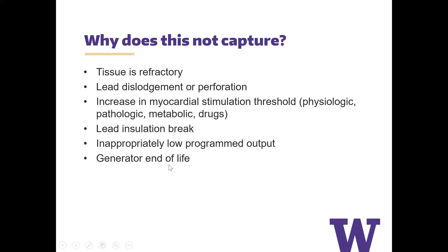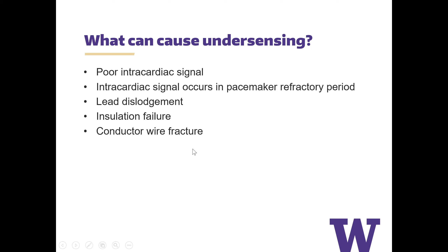And what can cause undersensing? If you have a cardiac impulse, but the pacemaker is not picking it up, it could be because it's a very poor intracardiac signal. The intracardiac signal can be occurring in pacemaker refractory period. The lead can be dislodged. You could have insulation failure. You could have a conduction wire fracture.